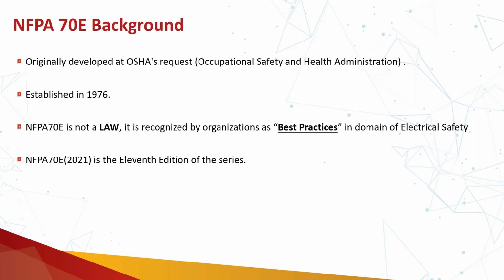Other organizations, like Easy Power and similar companies in the USA, conduct gap analysis against NFPA 70E best practices or recommendations, and they provide recommendations on what documentation and procedures you should have in order to comply with 70E requirements, issuing their own certificates. So there is no certification right now from NFPA or any ISO level related to NFPA 70E.